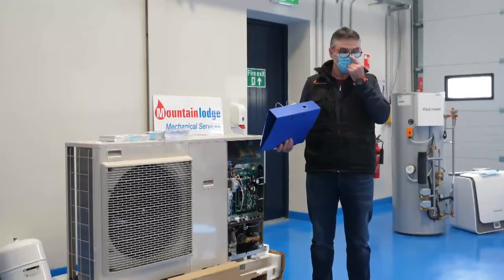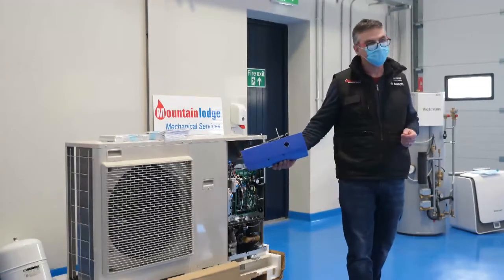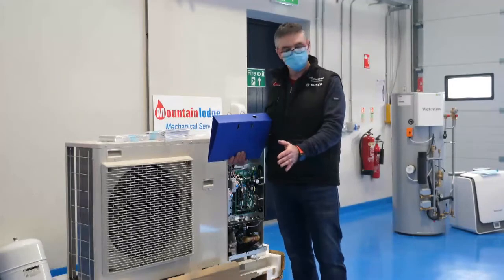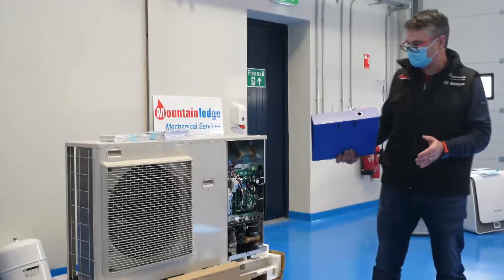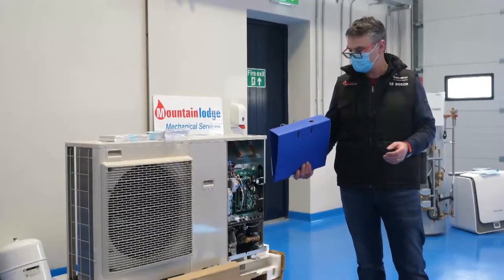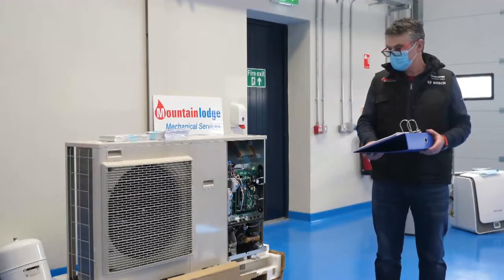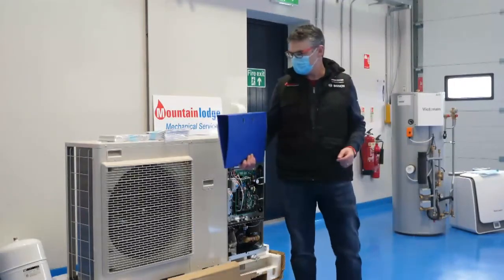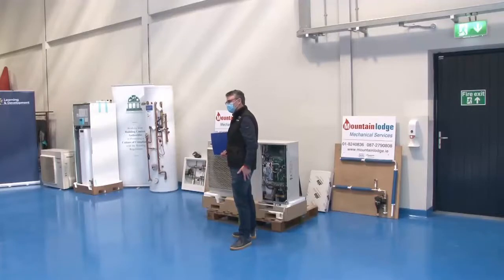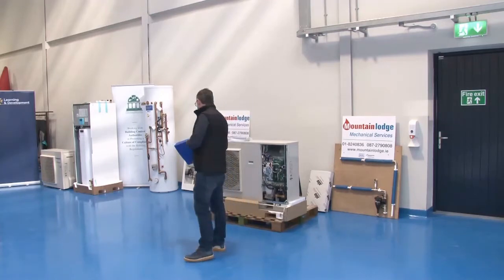If it's sited at a back door, another thing to take into consideration is that there is a blow off of these. When they're working, the air is quite cold. The minimum distance that you can put any obstacle, bins, anything else in front of it, the minimum clearance they need is a meter. So if when the house is finished somebody puts a temporary structure or something closer than 1 meter to the unit, it's going to interfere with the airflows, and it's going to cause the unit not to behave properly. So it's important wherever they're sited, there's no potential for any obstacles to come into that.